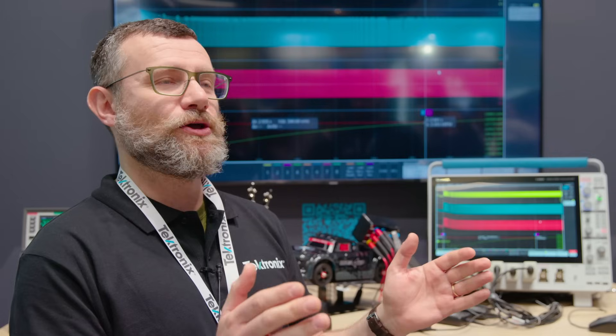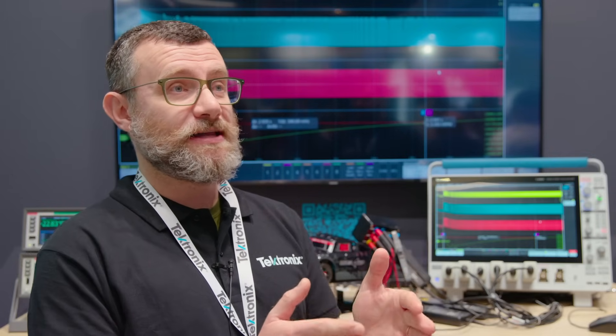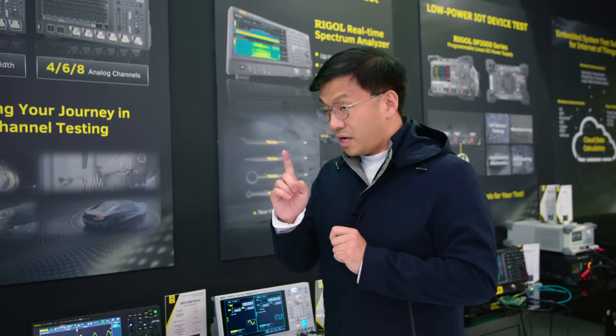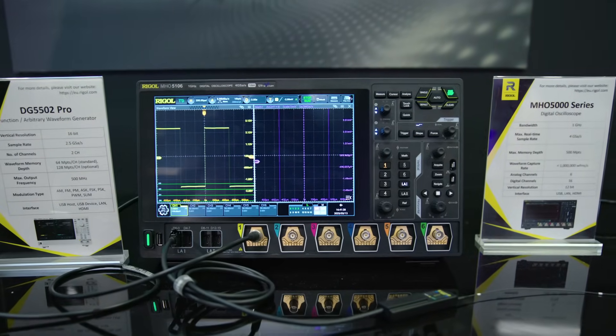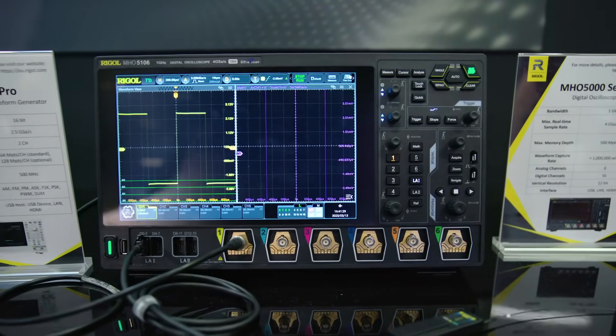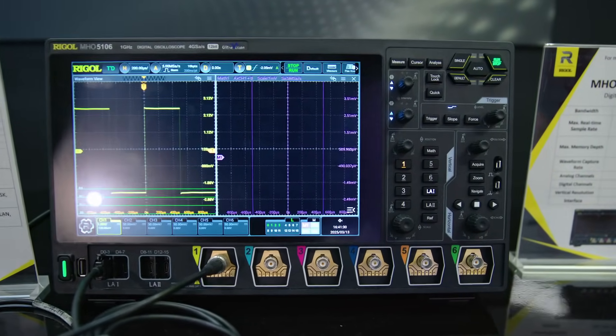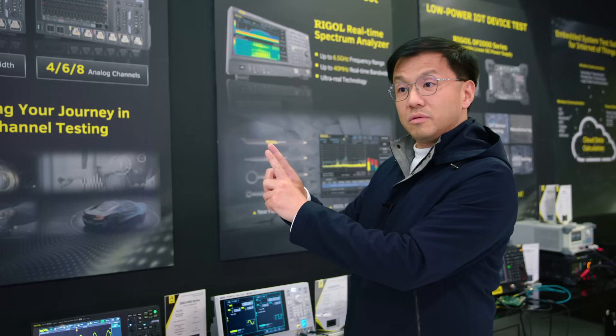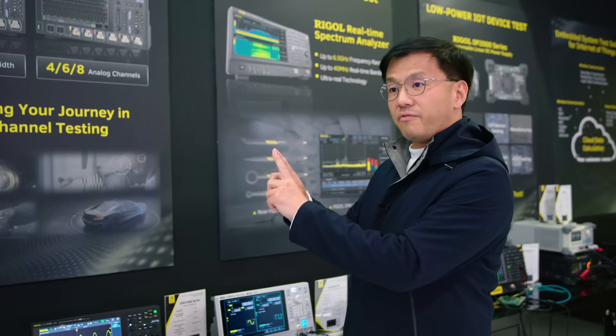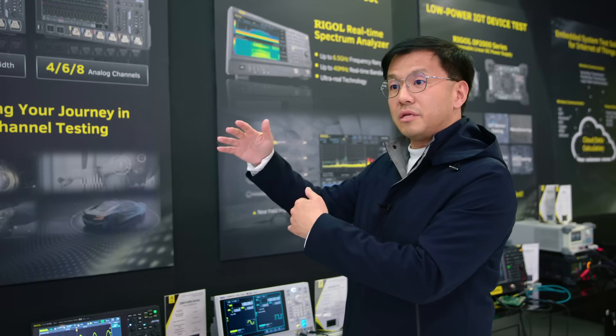The timebase is the same for everything — it's very precise with no jitter — so you can be sure you can really relate events that happen in time to one another. Most importantly, all eight channels can be synchronized simultaneously, meaning you can use a specific trigger point to see each channel's phase difference and time difference at the same time.